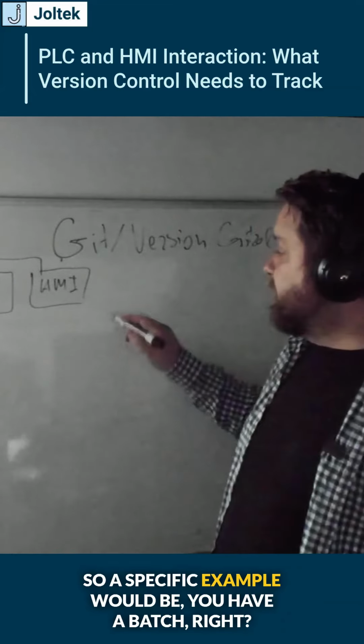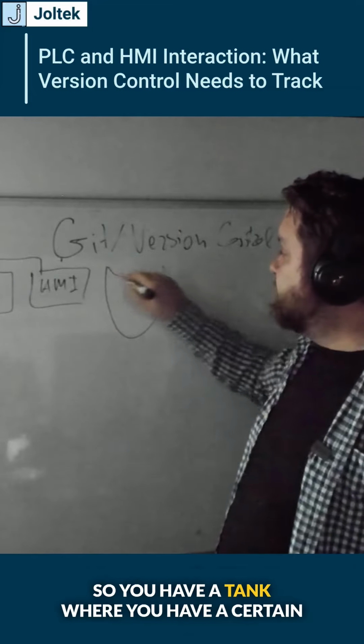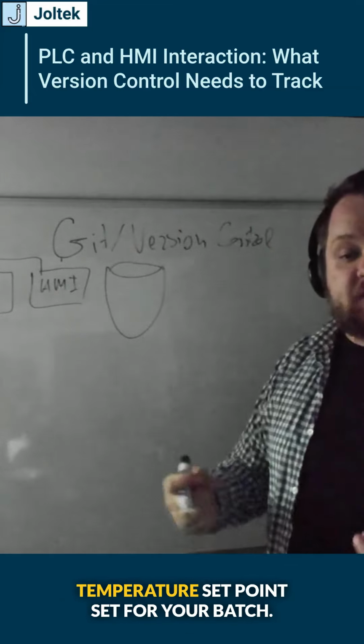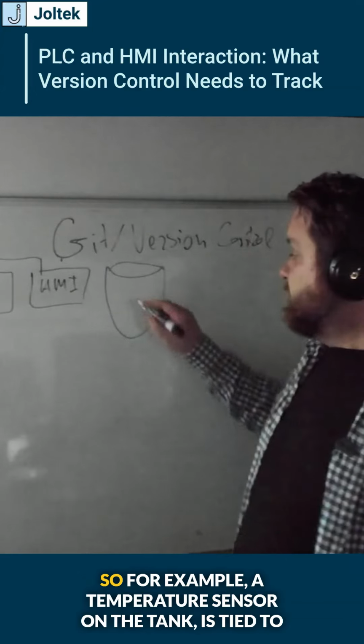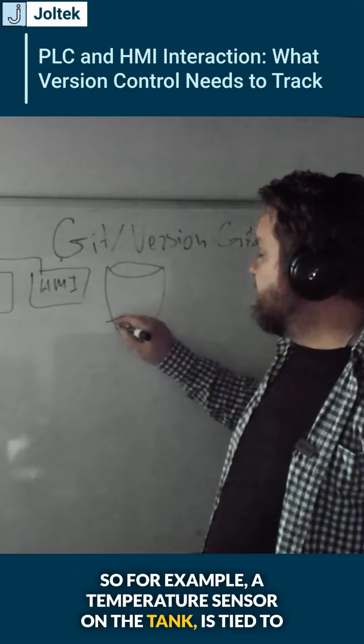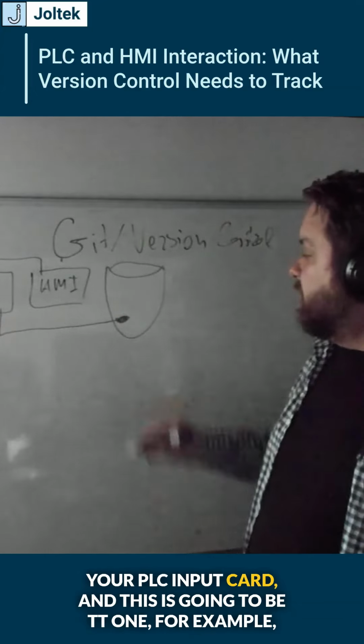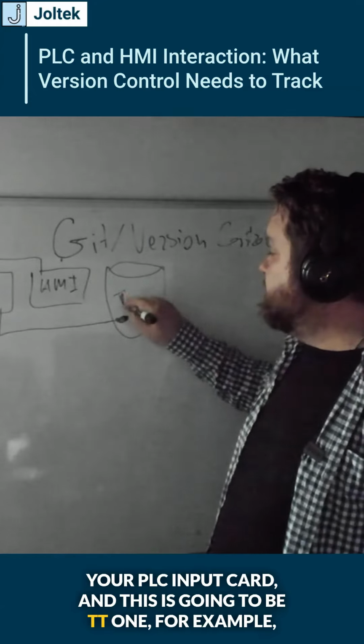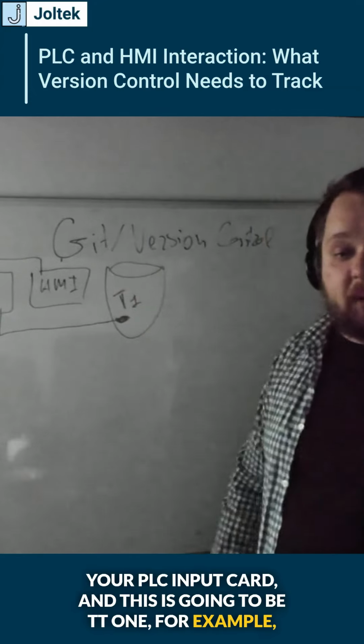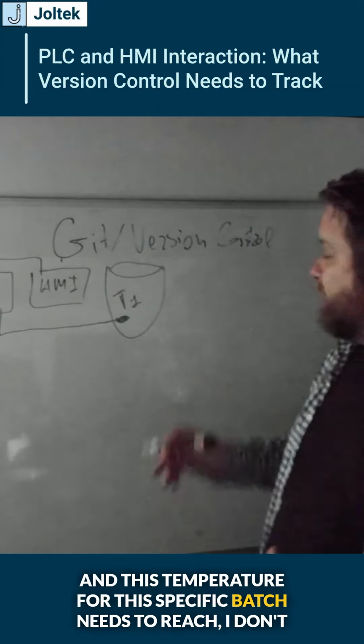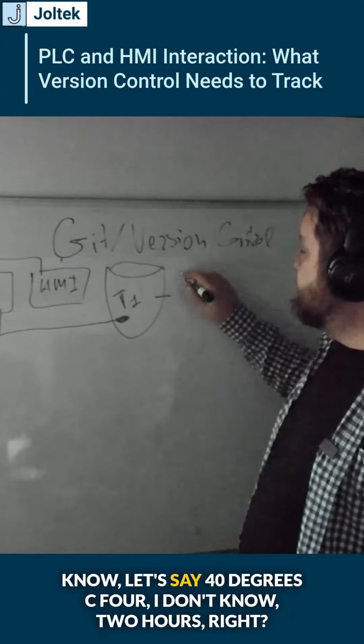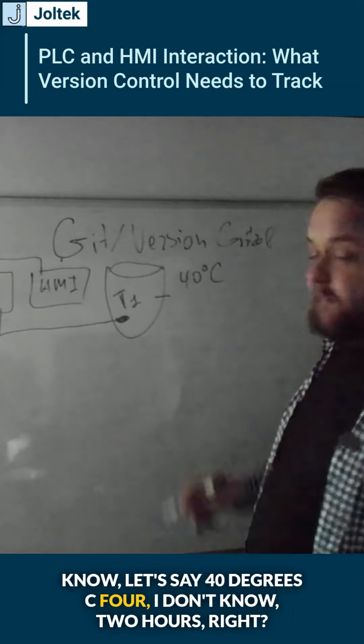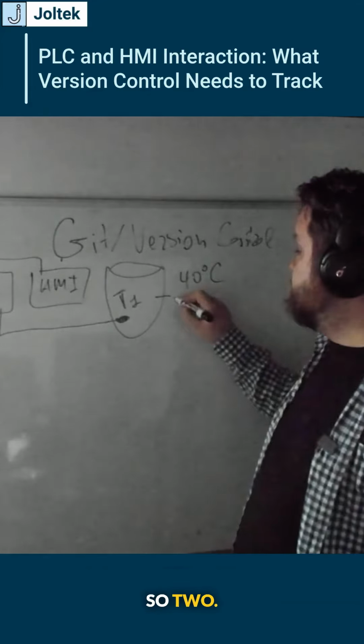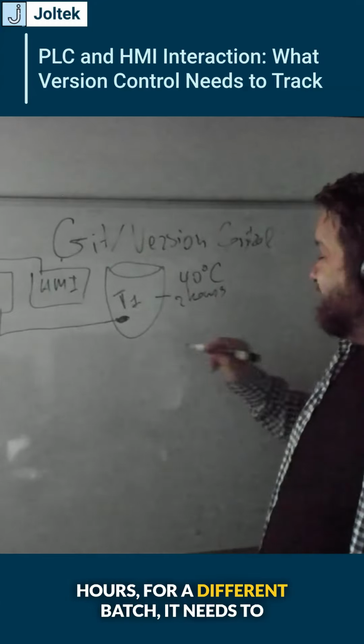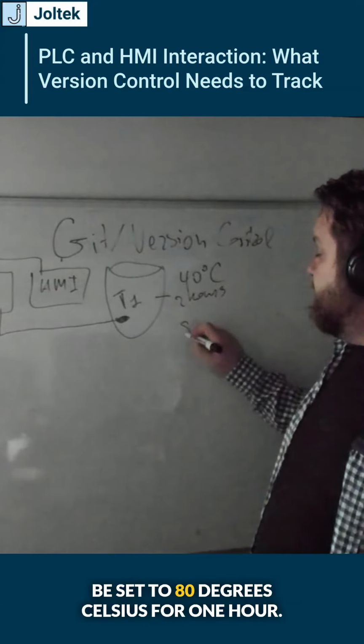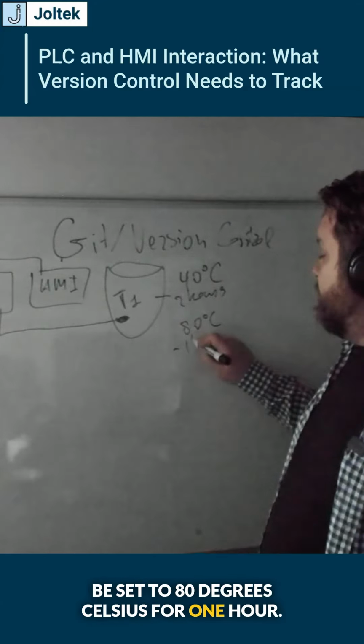So a specific example would be you have a batch, right? So you have a tank where you have a certain temperature set point set for your batch. So for example, a temperature sensor on the tank is tied to your PLC input card, and this is going to be T1, for example, and this temperature for this specific batch needs to reach, let's say, 40 degrees C for 2 hours, right? So 2 hours. For a different batch, it needs to be set to 80 degrees Celsius for 1 hour.